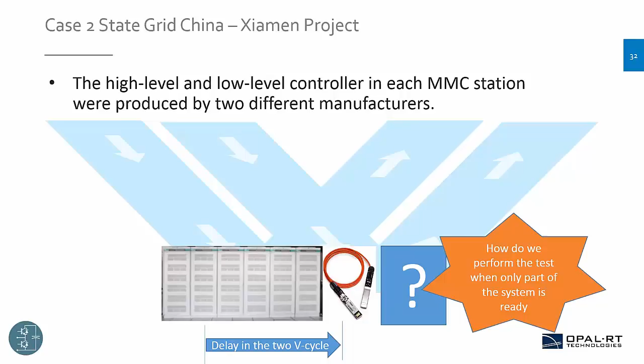In this case, the pole controller and the circulating current controller were the production equipment to be delivered to the field. They are connected to the simulator as in a standard hardware-in-the-loop test bench. Although the physical voltage balancing control was not available, the production code implemented on a similar FPGA can be used on the FPGA that was used to simulate the MMC valve. So the simulated VBC acquired the adapted voltage reference signal from the physical controller using the same HDLC protocol used in the field.